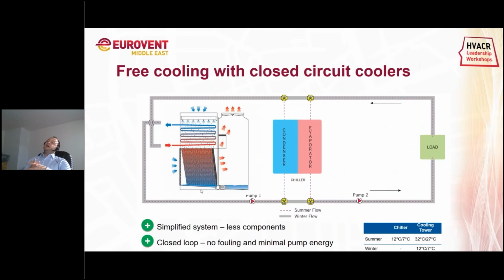When we want to show it on a diagram, free cooling, what does it mean? To give you a little bit more background, this is a traditional cooling tower chiller configuration, and on the right you have the load of the data center. In summer conditions, the data center is cooled by the chiller, and the condenser part of the chiller is cooled by the cooling tower. In winter conditions, when the ambient temperatures drop, the chiller can be omitted and the data center load is cooled immediately by the cooling tower. So this is what they call the free cooling.